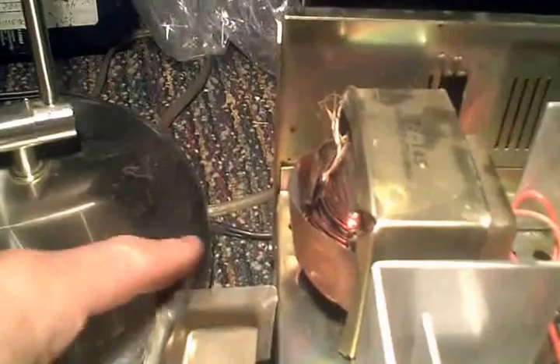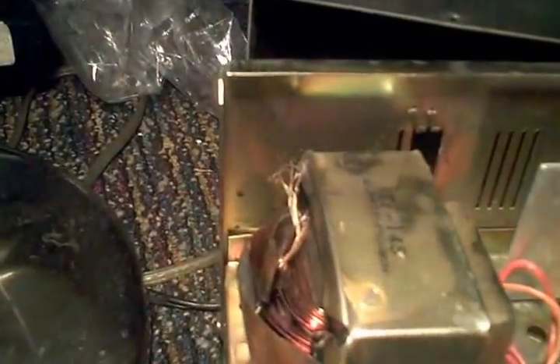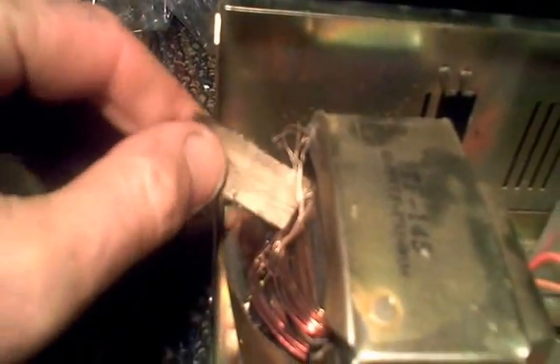I didn't think that bulge on the side there would possibly come from the lightning, but sure enough when I looked inside, this transformer had completely blown. And in fact, if you look at the windings, the magnetic flux coming off these windings was so intense it just blew them apart. Let you take a look inside there — that's a lot of power there to do that.